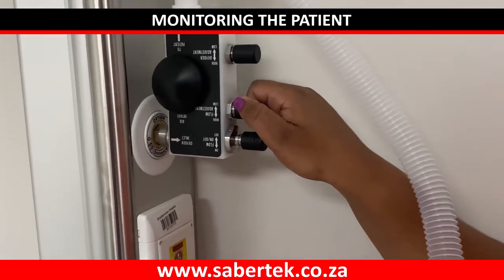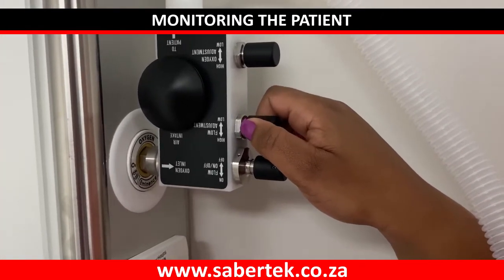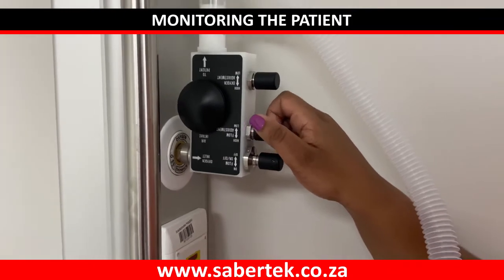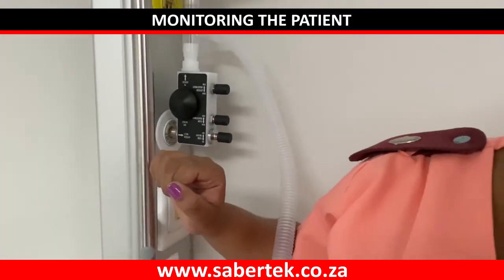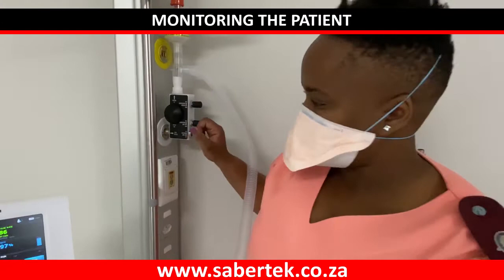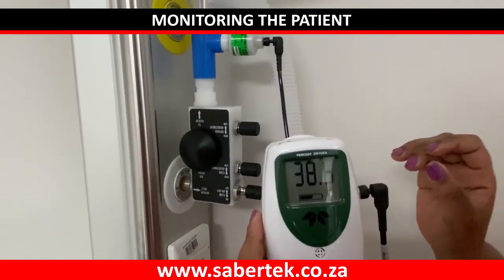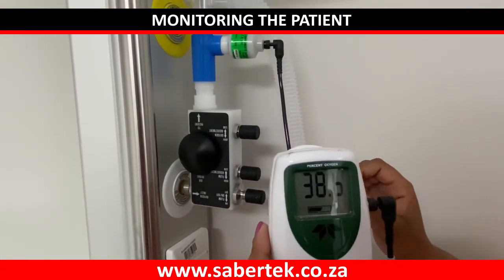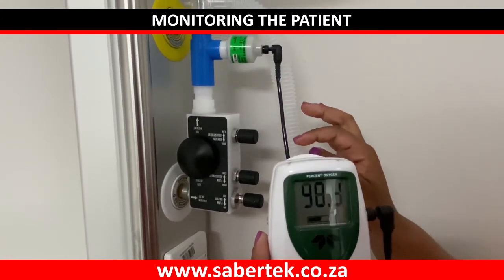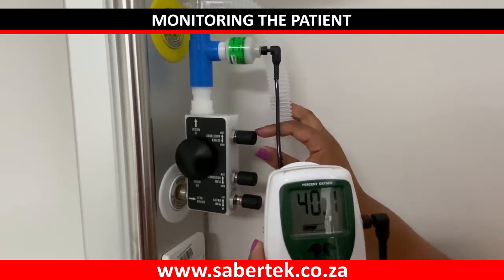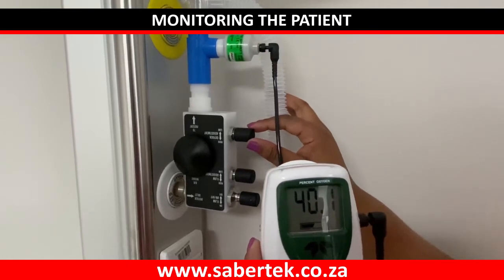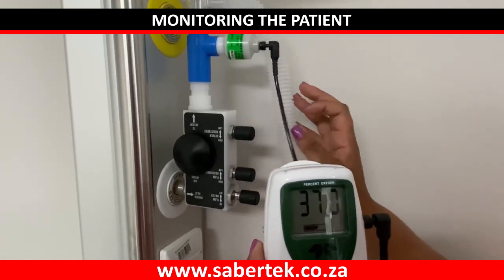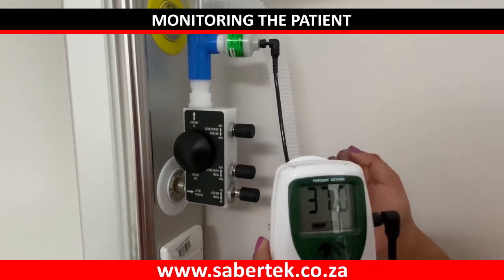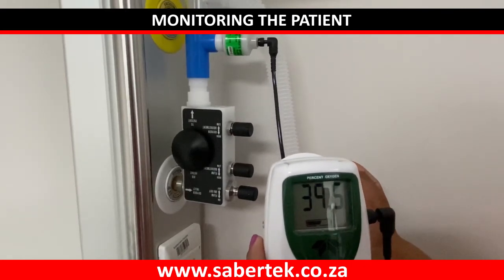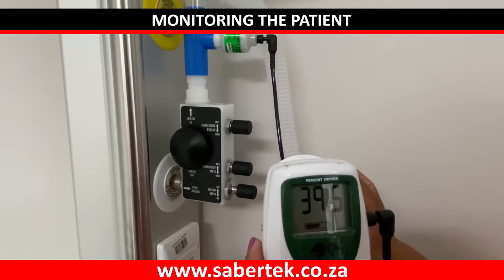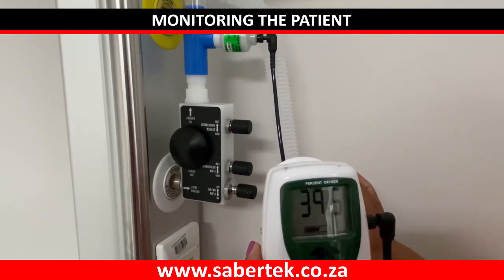If available, a pressure manometer can be connected to the mask to monitor the pressure during inspiration. If the pressure drops significantly, then the flow rate is too low. Check the patient's inspired oxygen level with the oxygen analyzer. Monitor the patient's blood oxygen saturation and check that there are no leaks in the complete system, using the SaberFlow CPAP without an oxygen analyzer. The patient monitoring parameters should be monitored closely, specifically oxygen saturation, SpO2, and partial pressure of arterial oxygen, PaO2.